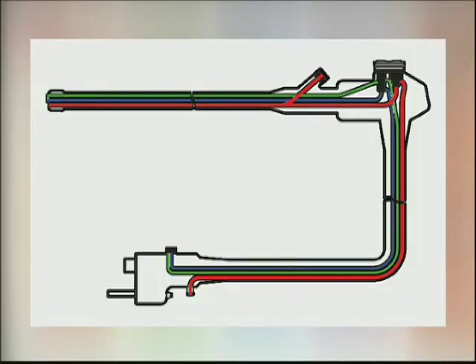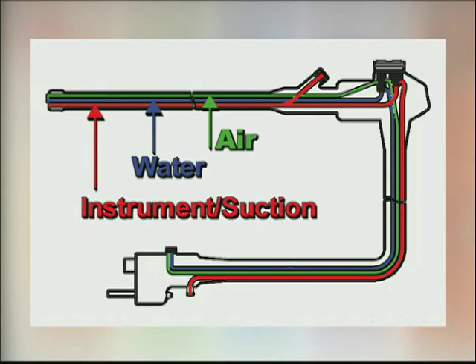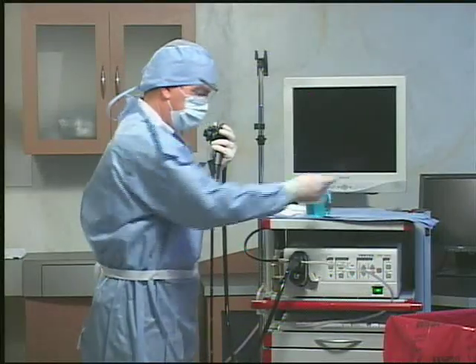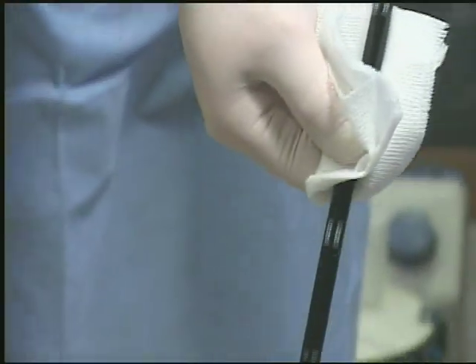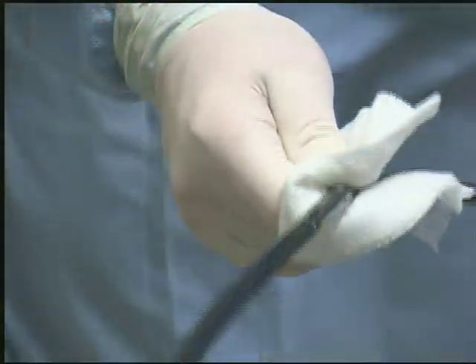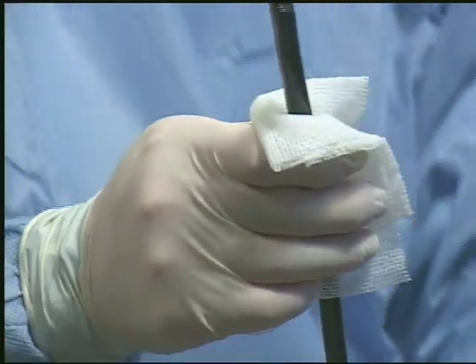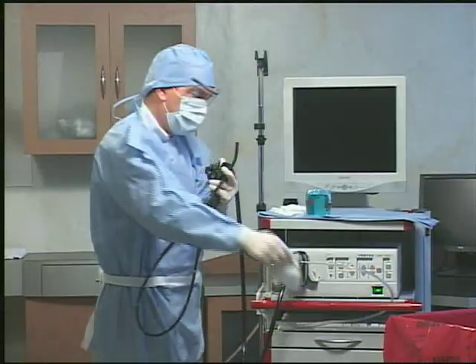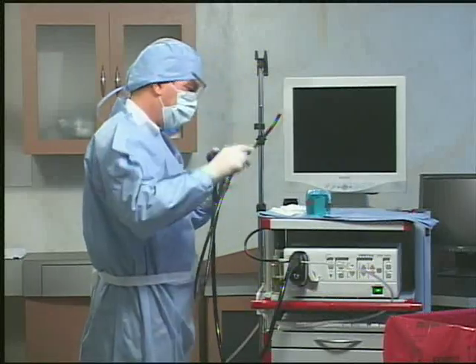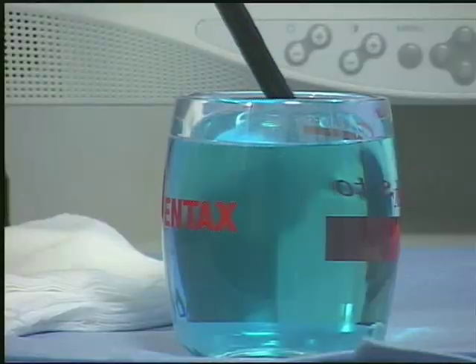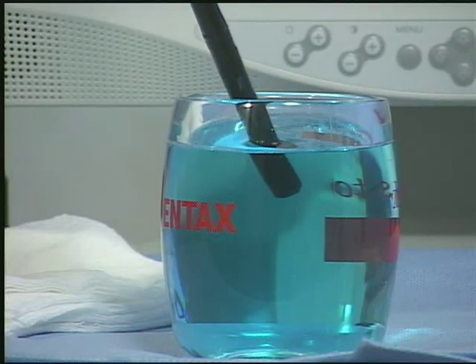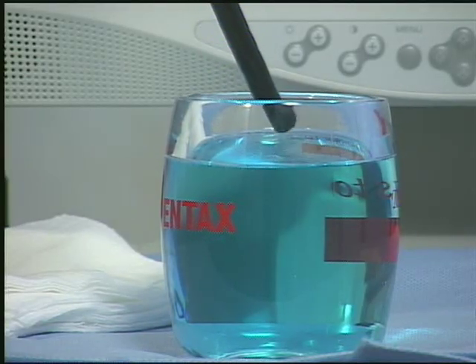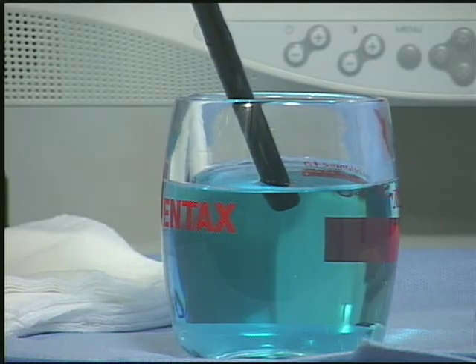The first instrument depicted in this video is a conventional forward-viewing upper GI endoscope or gastroscope, which has a total of 3 internal channels, one for air, water, and instrument suction. Immediately after removing the endoscope from the patient, gently wipe all debris from the insertion tube with gauze or the like, moistened with an enzymatic detergent solution. Place the distal end of the endoscope into detergent solution and aspirate through the channel for at least 5 to 10 seconds. Alternate suctioning of air and solution several times to create agitation for better pre-cleaning.